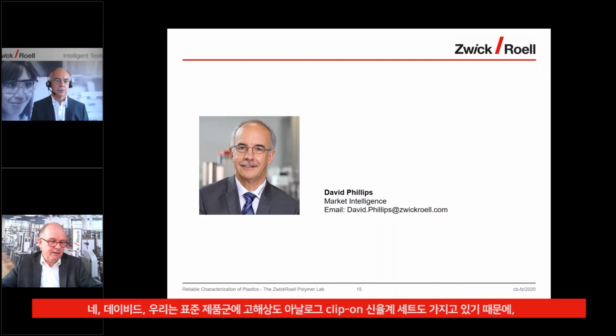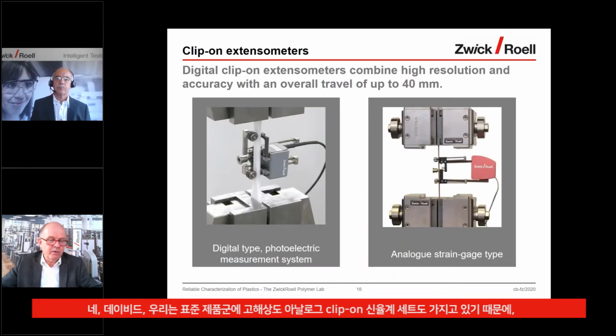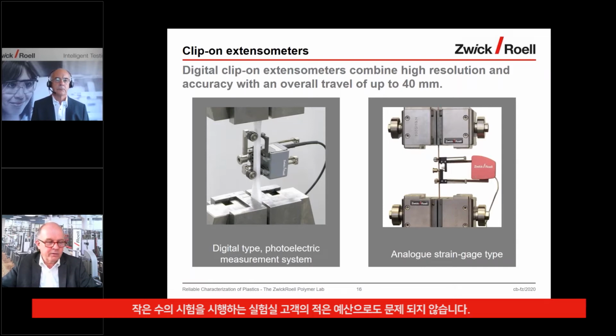Yep, David, you know we also have a complete set of high-resolution analog clip-on extensometers in our standard product range. This is not the problem, and this is for those customers who have a lower budget or for labs who just have a small number of such tests to be carried out. We also have digital clip-on extensometers, which offer some advantages compared to the analog technology.